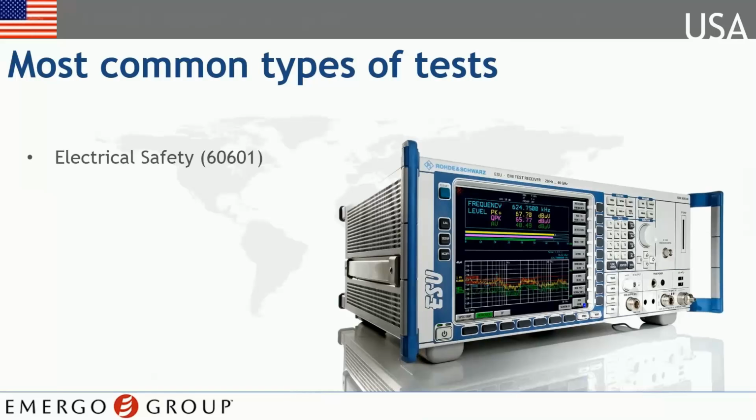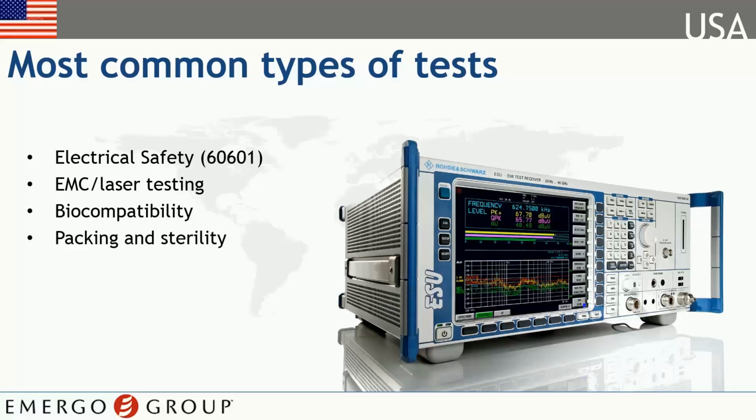Some of the most common tests include checking the electrical safety and effectiveness of medical electrical equipment, ensuring that a medical device does not emit any electromagnetic interference, testing the toxicity of the device when it touches the body, analyzing the sterilant residue and the radiation dose, if any, and testing the mechanical strength and performance of the device.